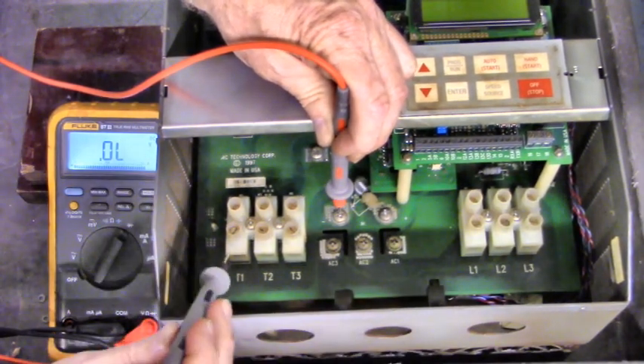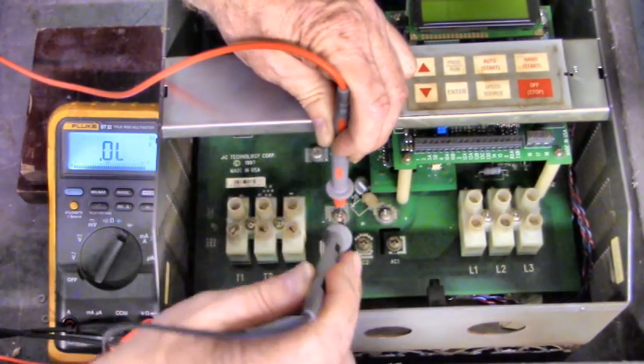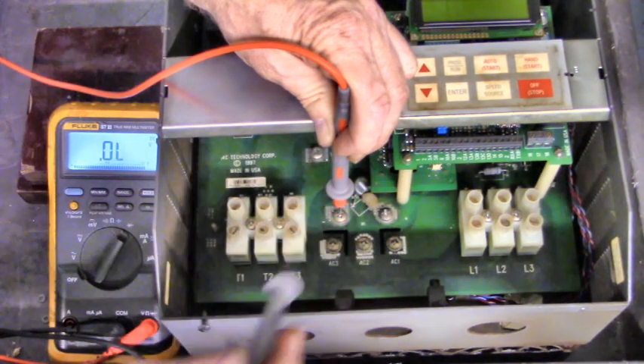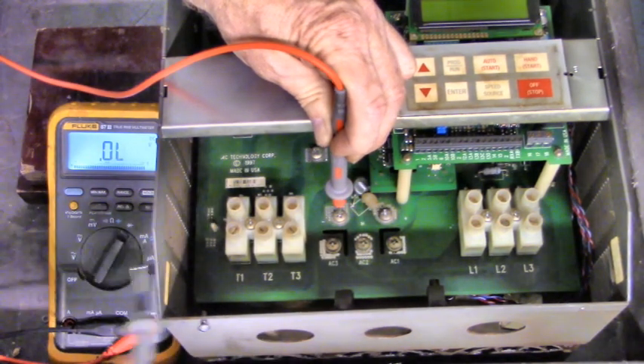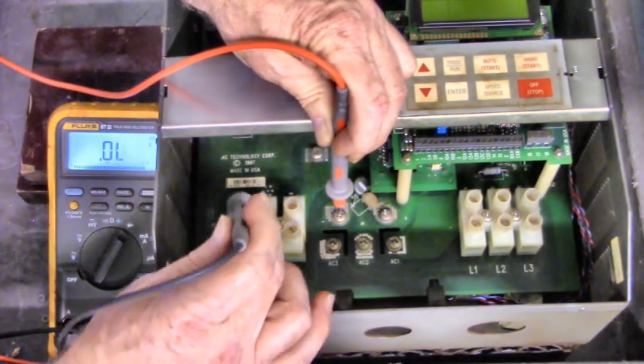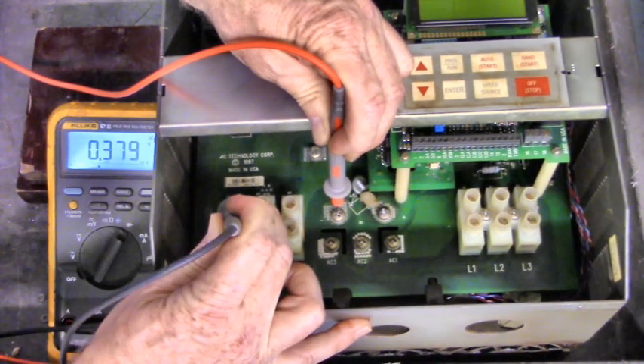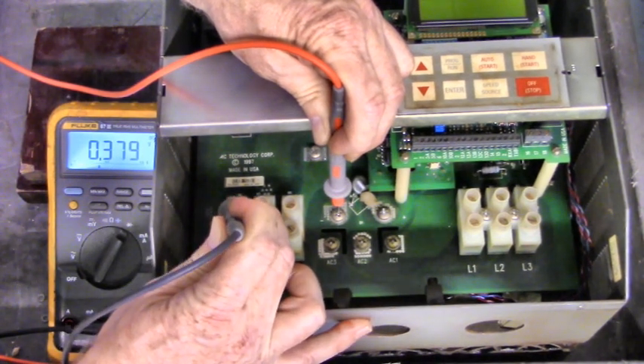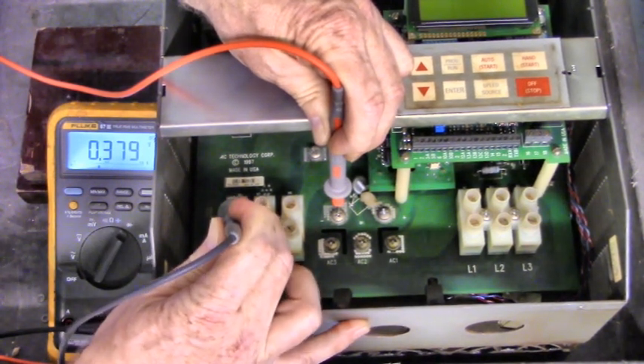Now, let's go to the IGBT. Leave your red lead on the minus terminal of the three-phase bridge. Put your black lead on T1, .379 volt diode drop.